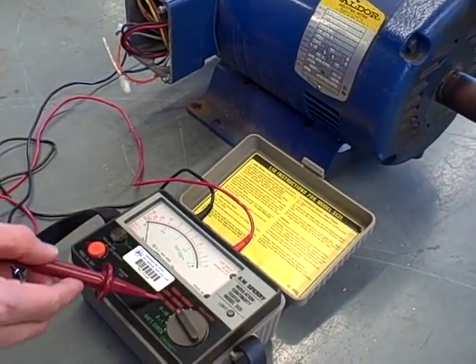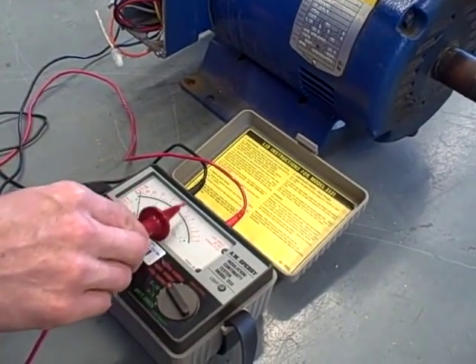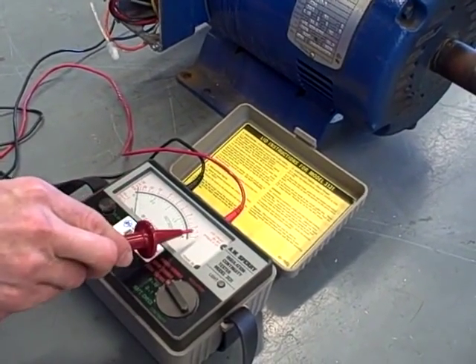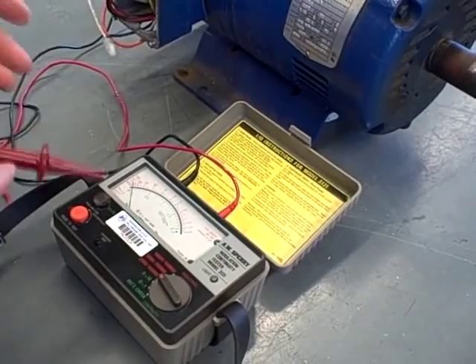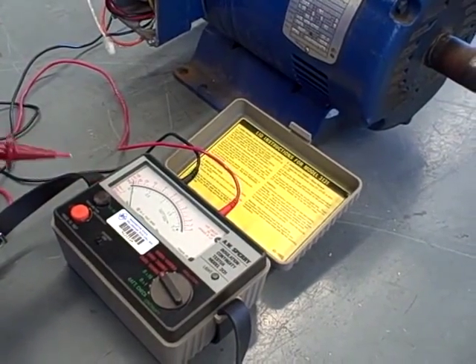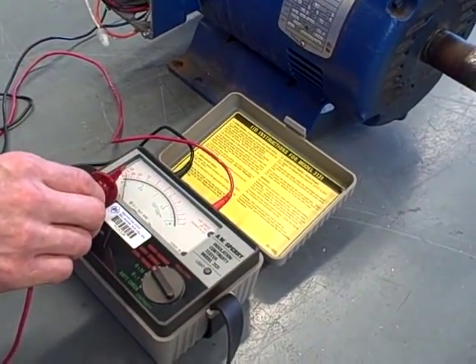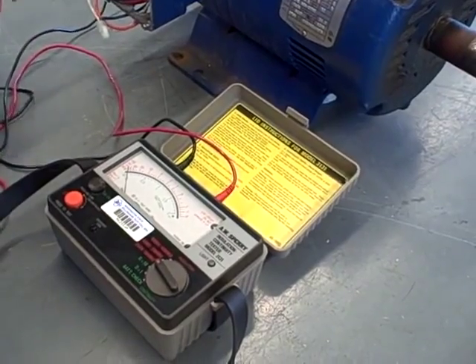Because this is on one of the orange scales, we read it on the top of the scale, and swinging all the way to the right means 0 ohms. That's a fault. We should not have 0 ohms. It should be a very, very large resistance between any phase winding and ground.